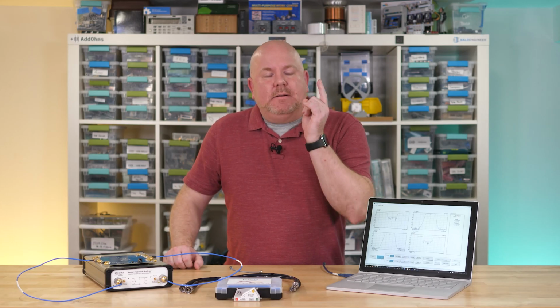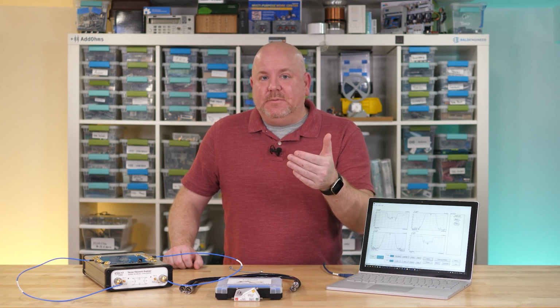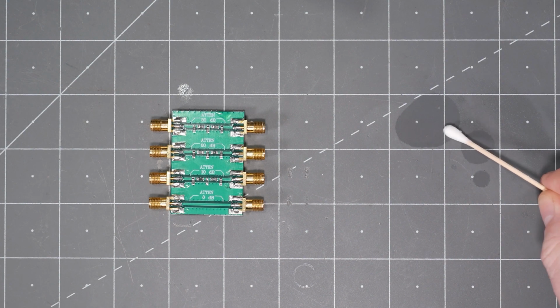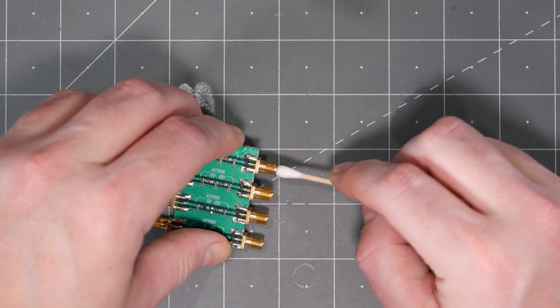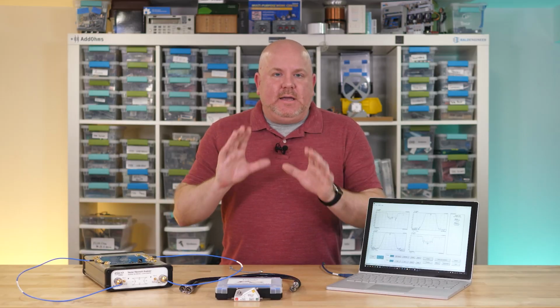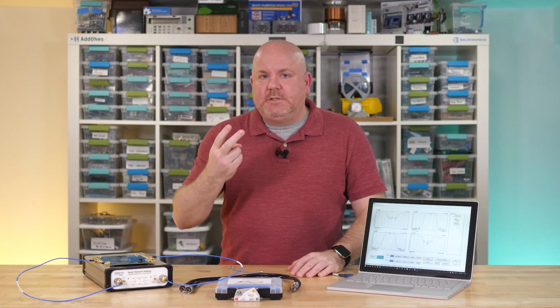Also, minimize the number of connector changes. Each adapter adds delay and ultimately will need to be calibrated out. Last, keep your connectors clean, especially the ground threads. It only takes a tiny bit of IPA and an electronics grade cotton swab. Make sure they are dry and that there is no cotton left over before you mate them to a connector. The big takeaway here is treat these connectors with care. Twist the nut, use a torque wrench, and keep them clean.